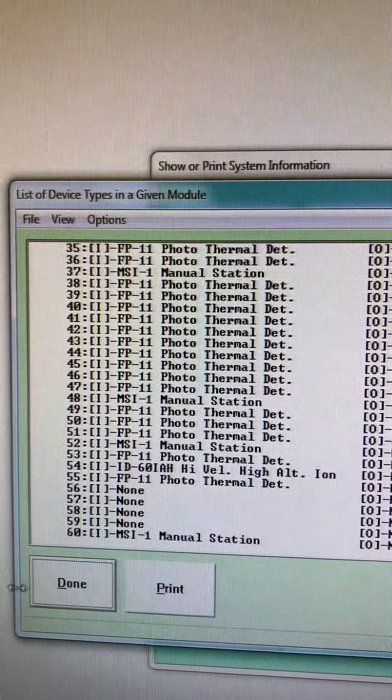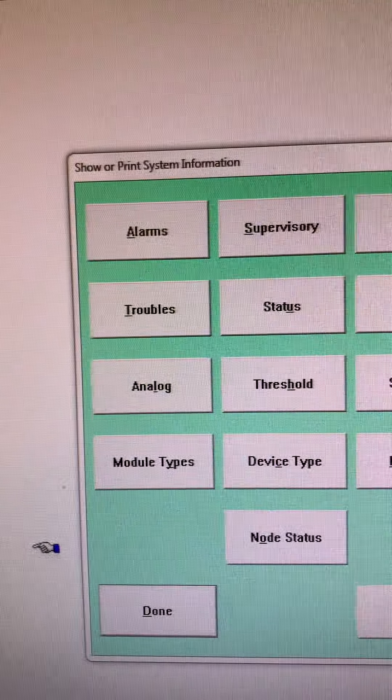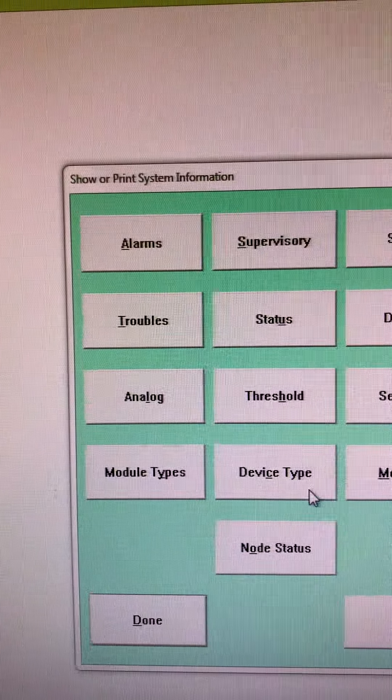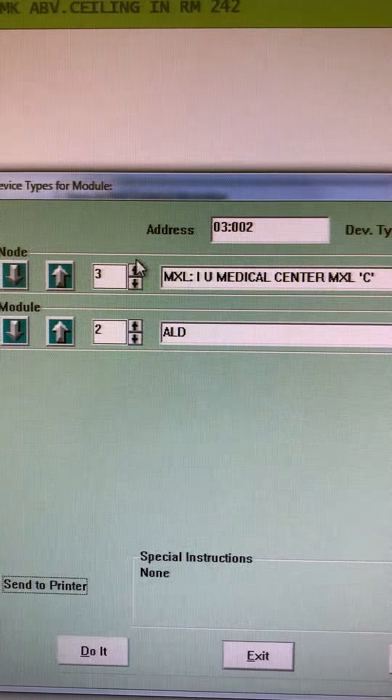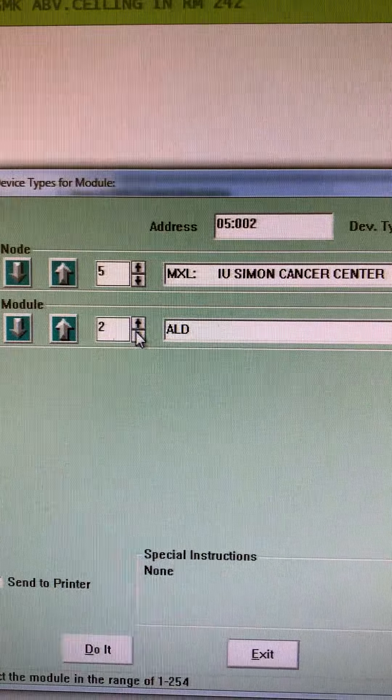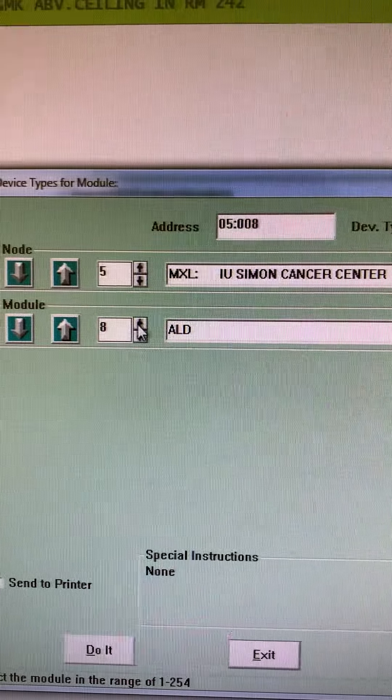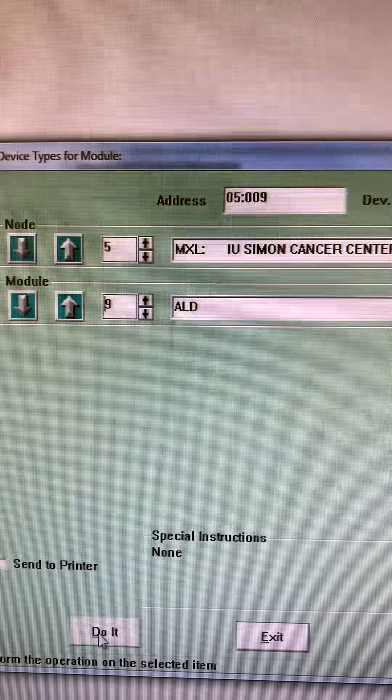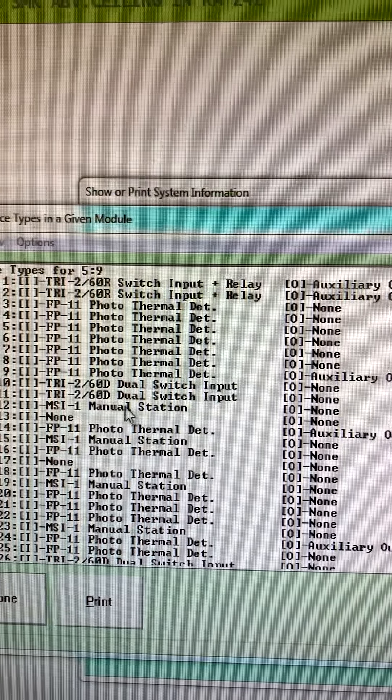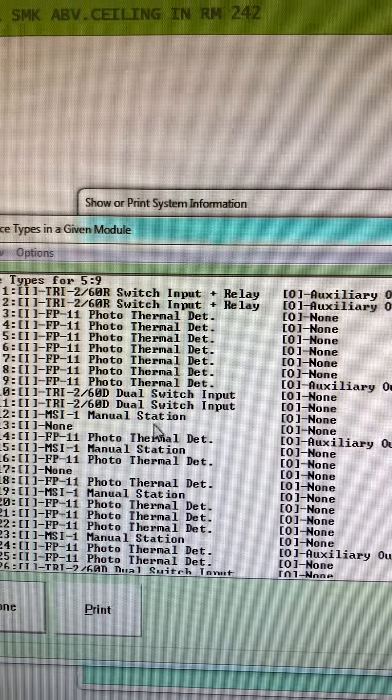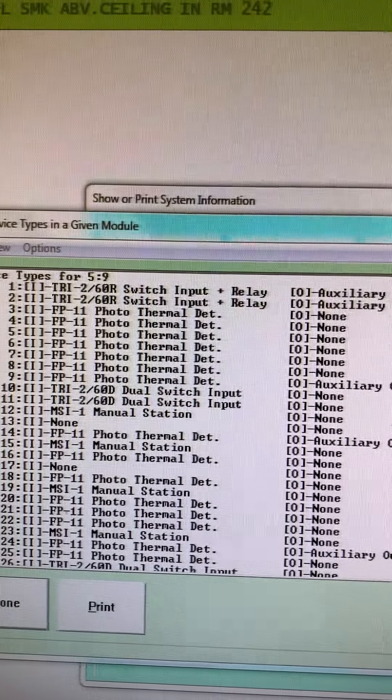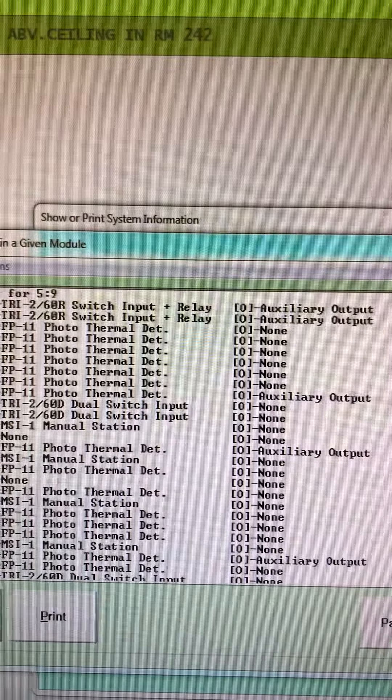There's a pull station down there. I can do this loop by loop for each panel. Let's just change it up a bit. Let's say I want to go to the Cancer Center, let's just do loop nine. Then again, see I get more detectors, pull station, dual switch inputs, likely sprinkler devices. It tells me the type, address here, what the functionality is and whatnot.